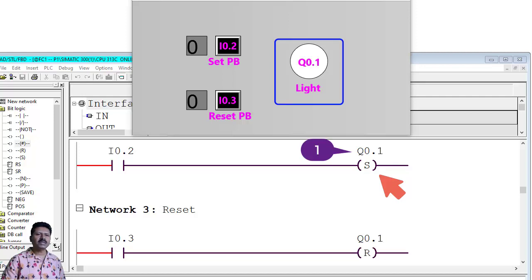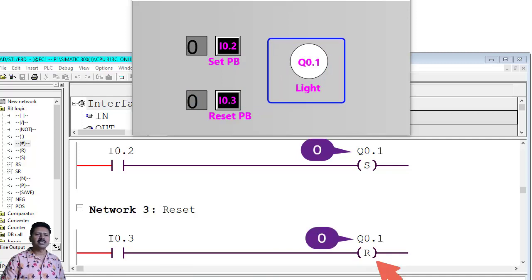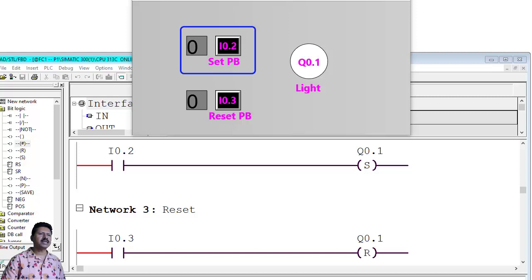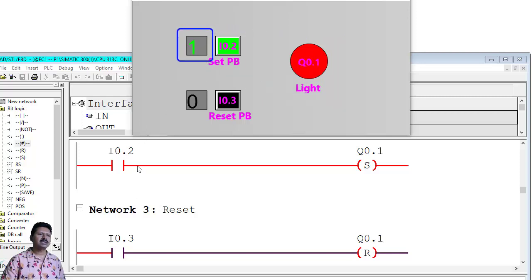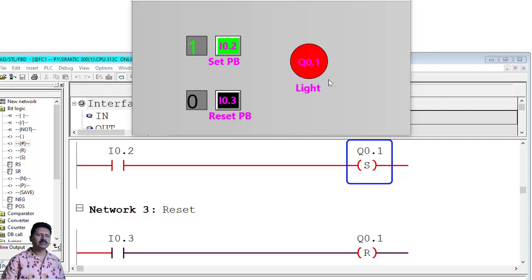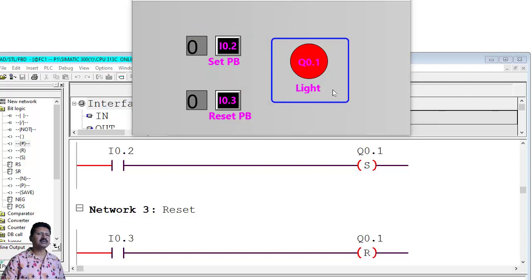Q0.1 will remain in logic 1 condition until we press reset push button I0.3. When I0.3 is pressed and released, the output will be reset — logic 0. Now I am pressing the set push button to turn the light on. Yes, the light is on — logic 1 signal is coming from the field, Q0.1 is logic 1, and the light is glowing. When I release the push button, the light remains on.